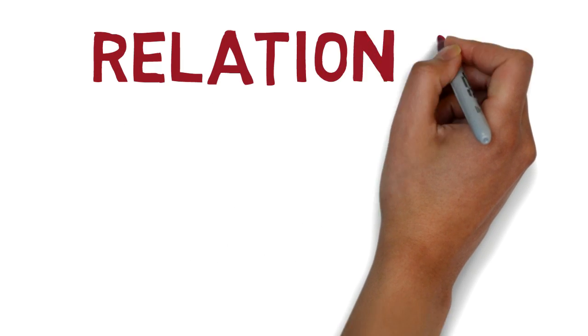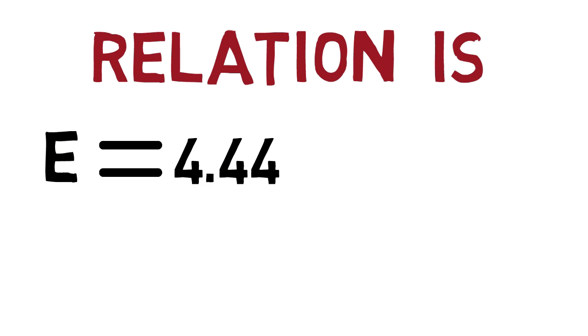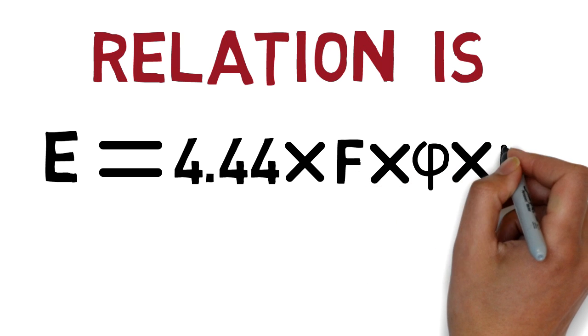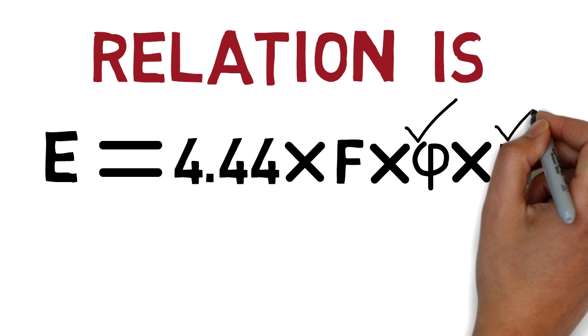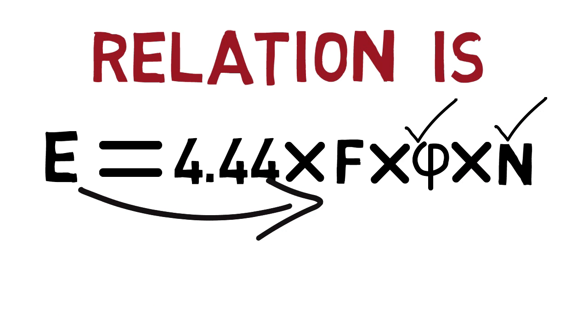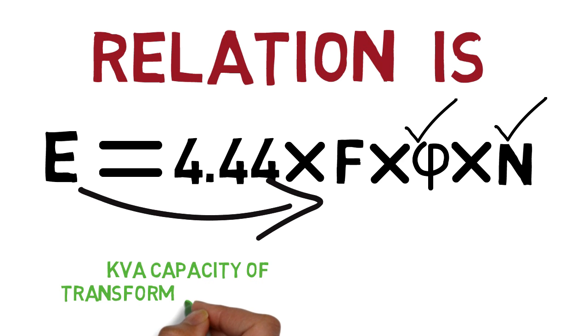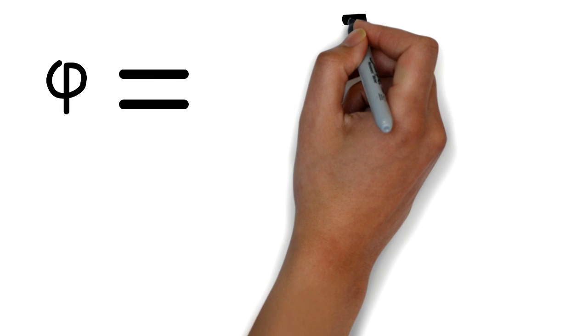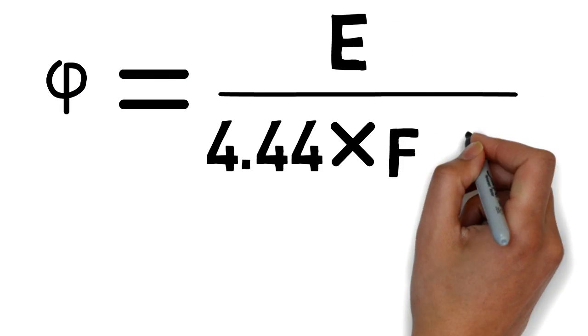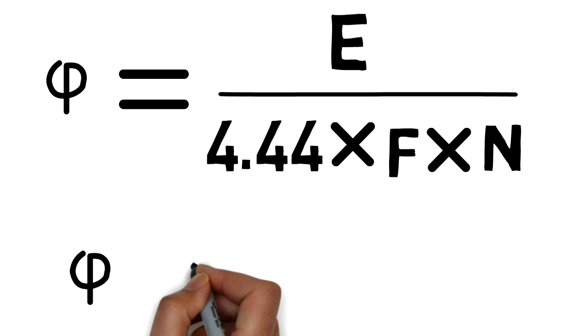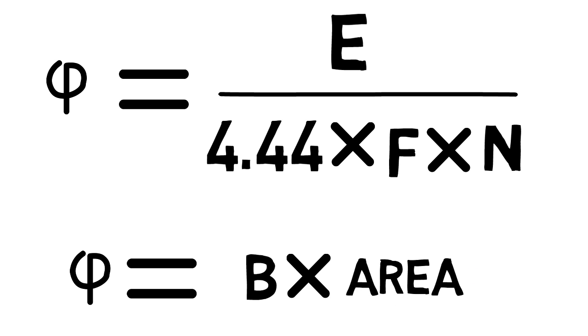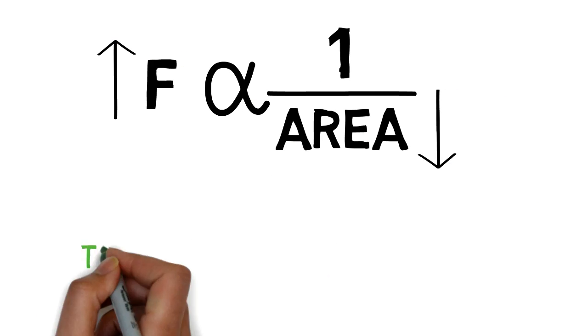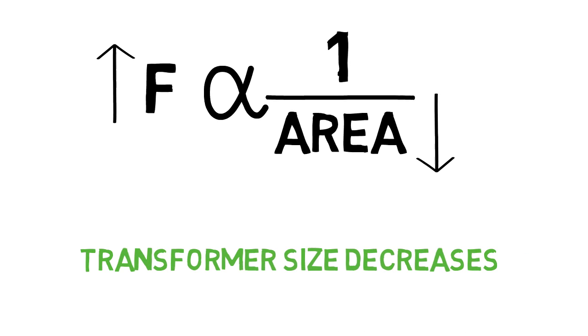The relation is given as induced EMF is equal to 4.44 into frequency into flux induced in core into primary turns. So, keeping flux and primary turns constant, the induced EMF is directly proportional to frequency. Thus, the overall kVA capacity will increase with increase in frequency. And also from this formula, we can find out flux induced is equal to induced EMF upon 4.44 into switching frequency into turns. As we know, the flux induced is equal to flux density into cross-sectional area of flux path. Hence, as frequency increases, the area decreases which decreases the size of transformer.